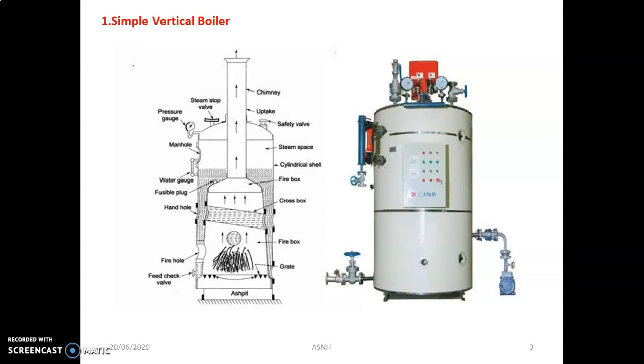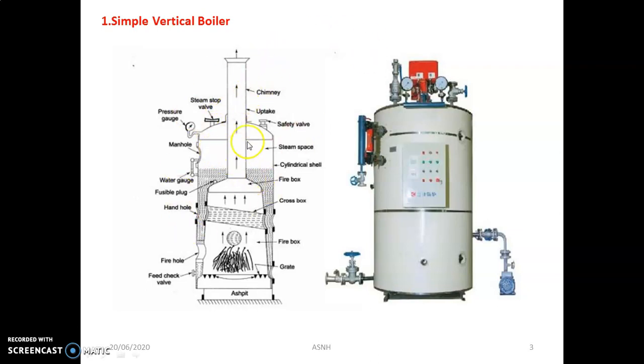The boiler also consists of a number of mountings including safety valves, steam stop valves, pressure gauges, and manholes. Each mounting has its own application. The manhole is necessary to clean the furnace area and assist with maintenance, as well as to clean the inner portion and the chimney. The pressure gauge is required to know the steam pressure, the safety valve is important per IBR safety norms, and the steam stop valve is necessary for emergency purposes.